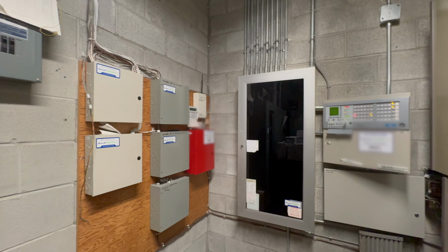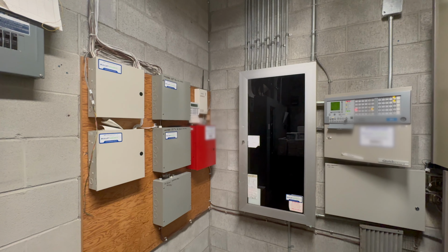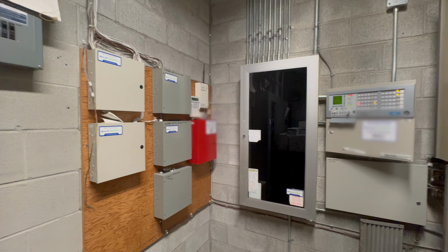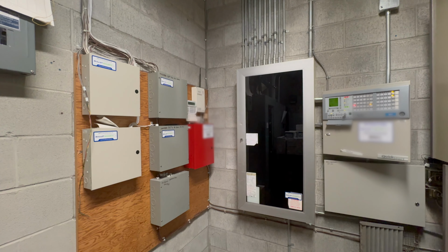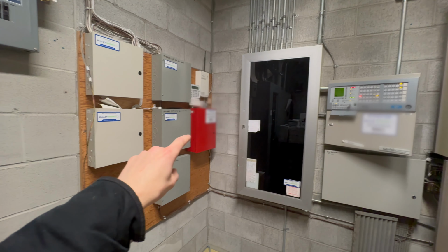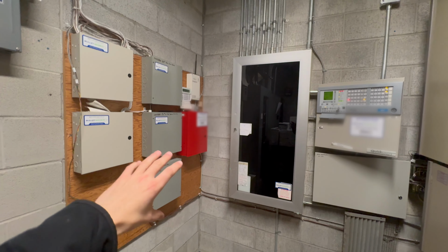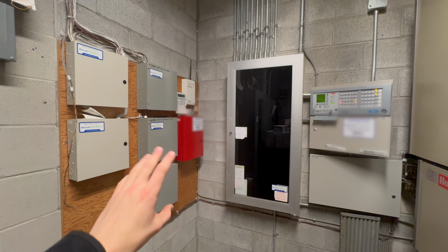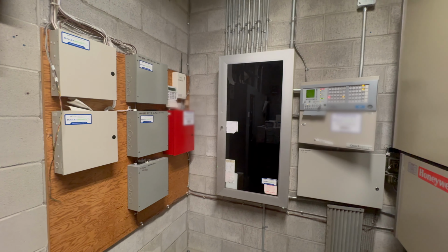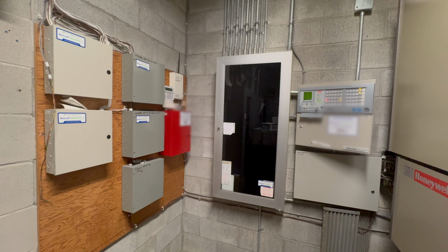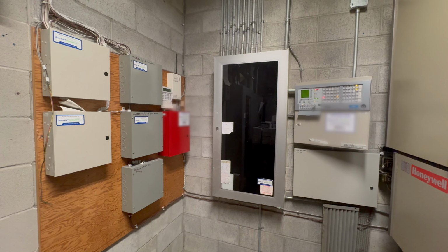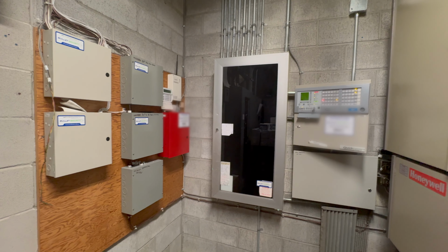You will see many grandfathered in setups where they're just using the intrusion alarm to monitor the fire alarm panel. That is fine if it's existing, but any new install or upgrade should be done properly with a separate ULC listed fire monitoring panel. That's how we do it here. We never use the phone lines coming straight out of the fire alarm panel. It always goes through a separate monitoring panel. That's just how it is in my location.